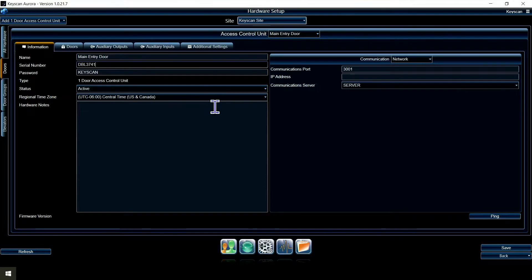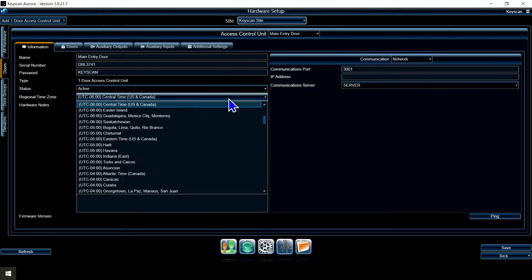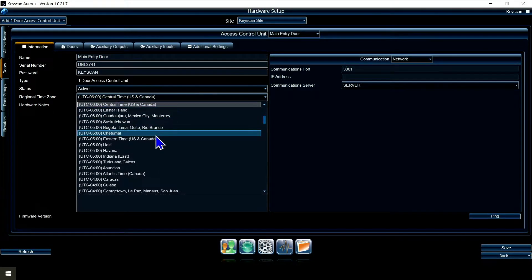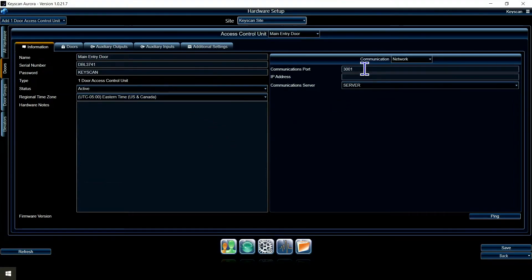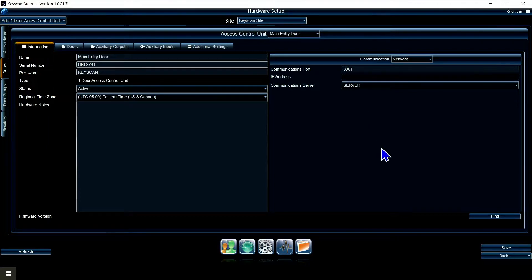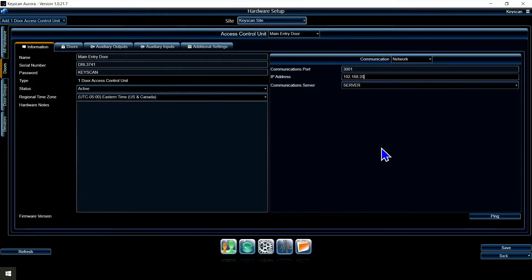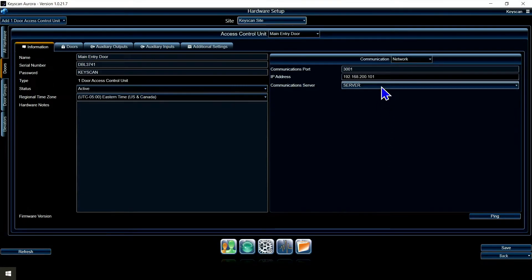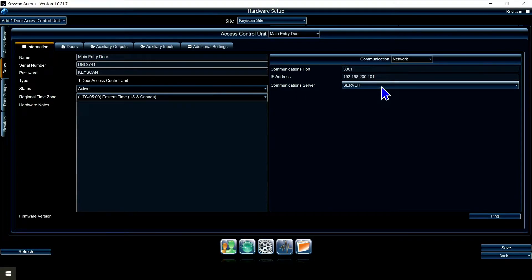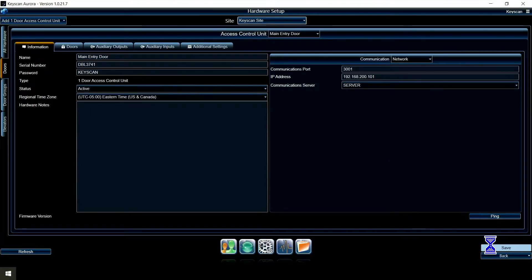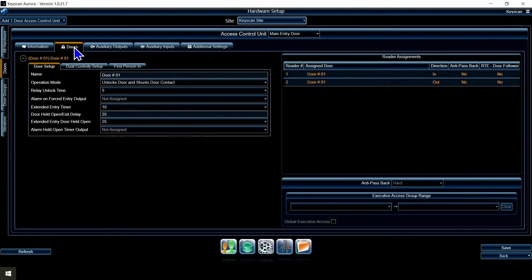Password Keyscan, that's fine, that's kind of built in the panel. Don't really want to change that unless you want to do a lot of extra work. What's your time zone? Well, we're in Eastern time here, so I'll put that. COM port is always 3001 unless you change it. My IP address, I've got this panel set on this IP address as my demo, and the communication server is the server we set up in the software installation. That's just the name of my computer.